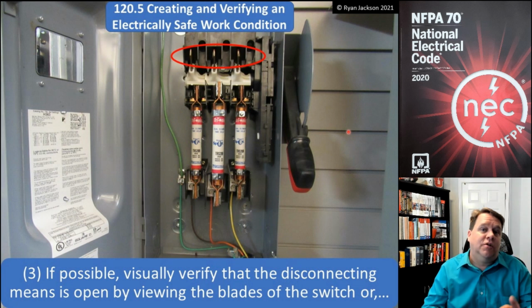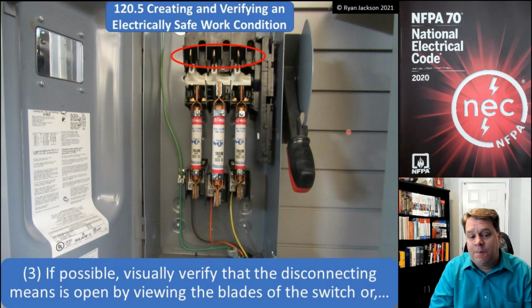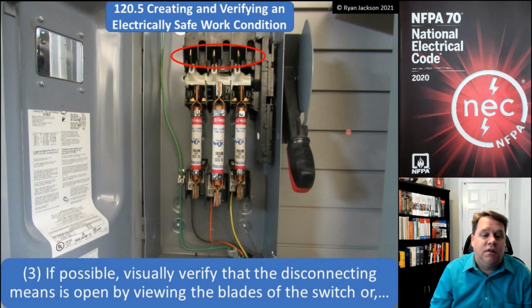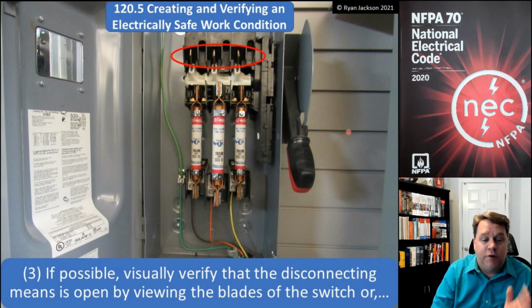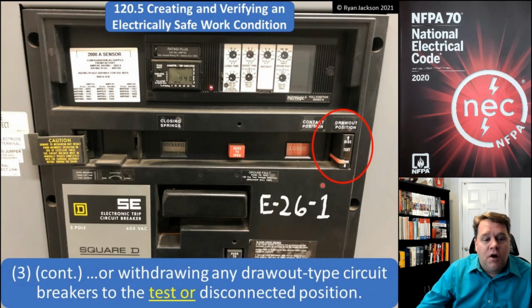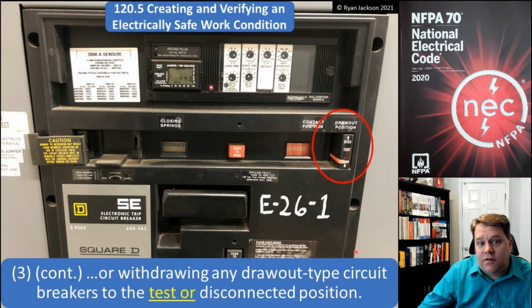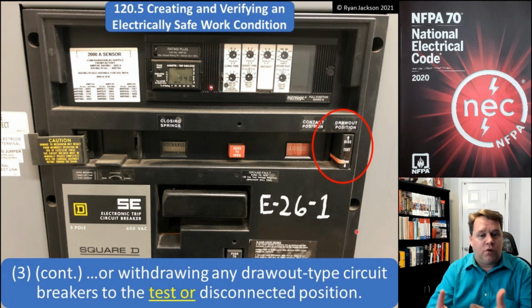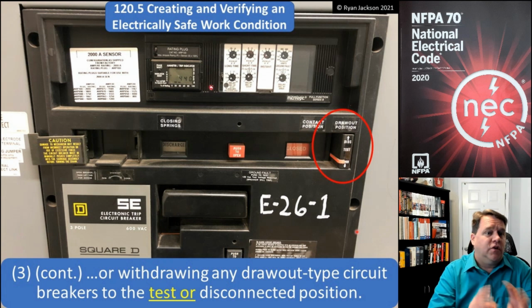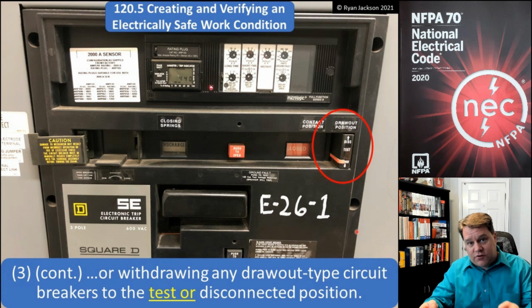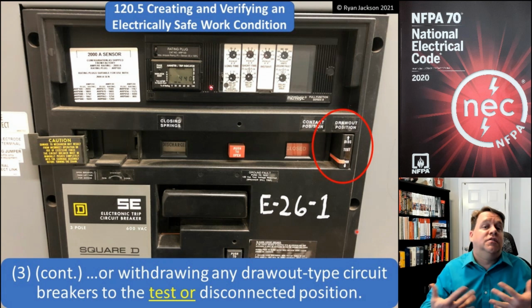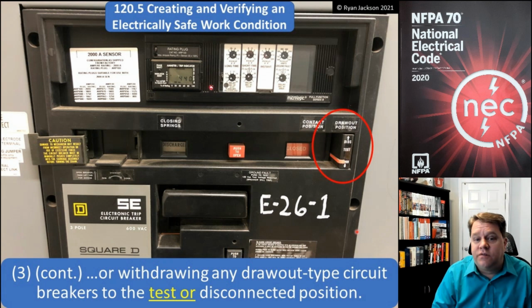If it's possible, if it's feasible, if it's safe, let's visually verify that the disconnecting means is open by viewing the blades, or withdrawing any draw-out type circuit breakers to the test or the disconnected position. So on the circled item here, you can see that we've drawn that thing out. Once I push it in or do whatever is necessary to draw the circuit breaker out, if I can visually see that it's drawn out, that gives me an additional measure of safety.